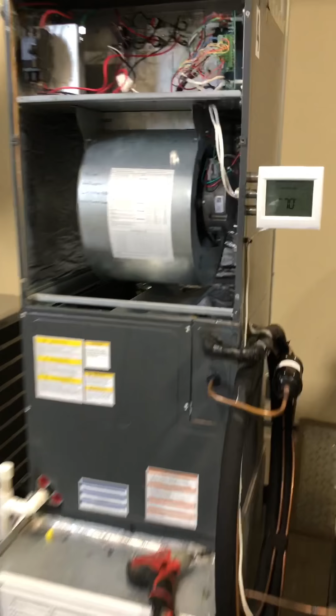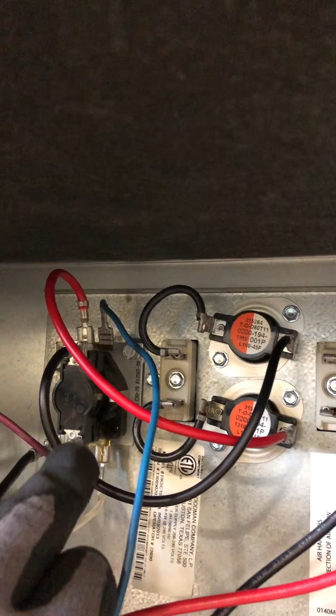To control those, we have what we call a stack sequencer. And again, I've verified that the power is off to this. I also have my breaker off, and I have tested the power with my multimeter. This is a stack sequencer. Get that red wire out of the way there. The reason it's called a stack sequencer is because there are actually two switches. You can see there's one switch here, and there's another one down there. There are two heating elements inside this, so there are two switches on the stack sequencer.